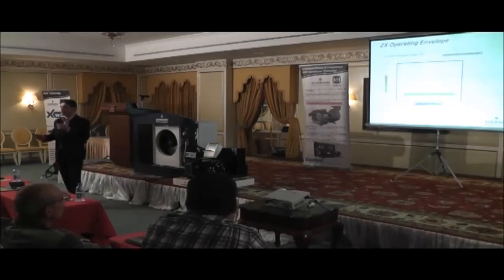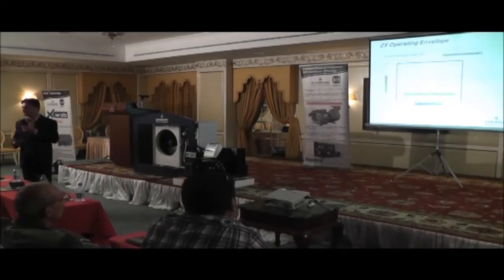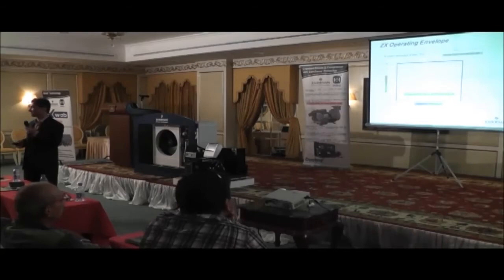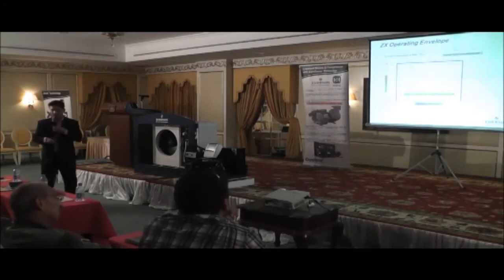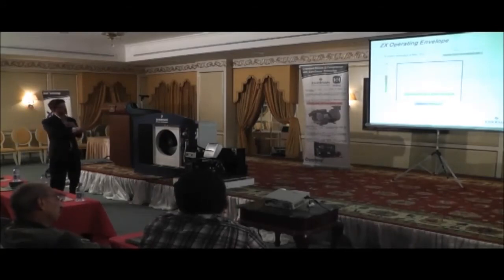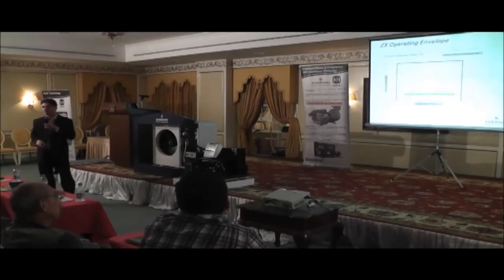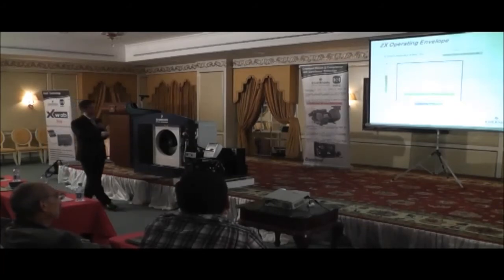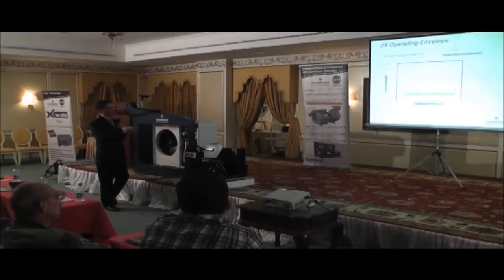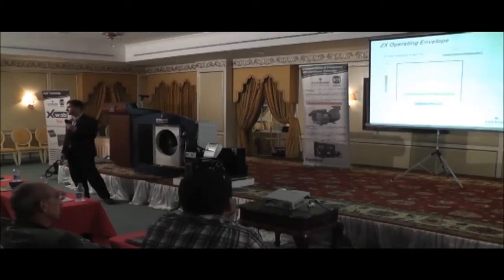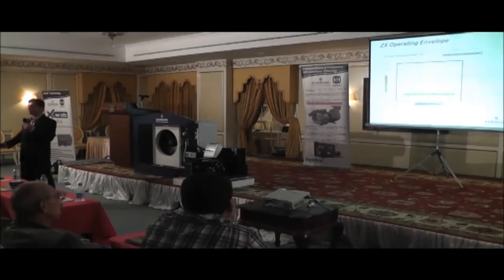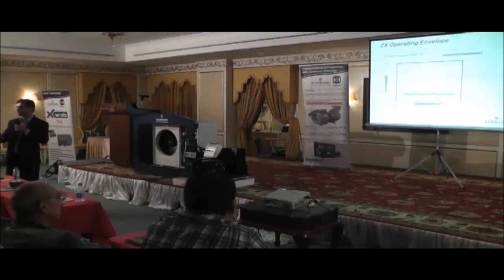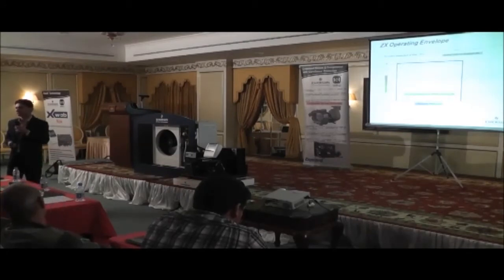So now you're asking me, why do we use suction line liquid injection for the medium temp units? Because we normally only use it for low temp. Well, with hermetics, we need to do this to give you a much bigger operating envelope. So for the chiller unit, you can run from -15 all the way up to +5 at up to 50 degrees C ambient. And the only reason we can run to these high ambients is by introducing liquid injection to cool down the compressor. If we didn't do that, this compressor would overheat.